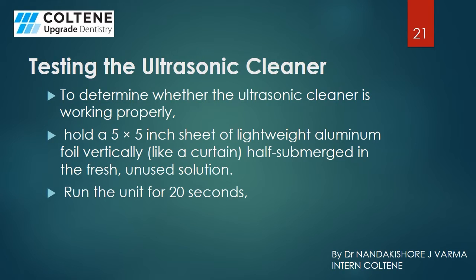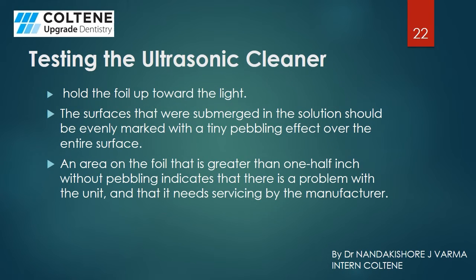Let's see how to test an ultrasonic cleaner. It is to determine whether the cleaner is working properly. Hold a 5 x 5 inch sheet of lightweight aluminium foil vertically like a curtain, half submerged in the fresh unused solution. Run the unit for 20 seconds. After running the unit for 20 seconds, hold the foil up towards the light. The surface that was submerged in the solution should be evenly marked with a tiny pebbling effect over the entire surface. An area on the foil that is greater than 1/2 inch without pebbling indicates that there is a problem with the unit and it needs servicing by the manufacturer.